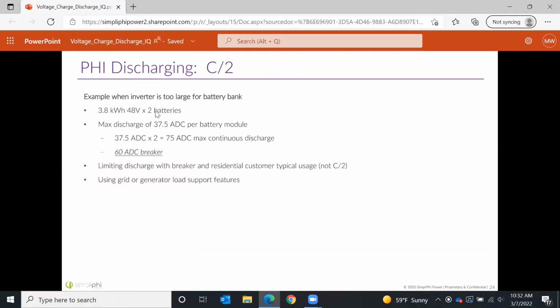We've got two batteries and they're 48 volts, so their max continuous discharge is 37.5 amps each. This is 75 amps total. And to protect the batteries, we're going to use a 60 amp breaker. We'll explain this a little more in detail as we go on. But first and foremost, when I see a 60 amp breaker and each of those batteries have an 80 amp surge for 10 minutes, there's almost no way that you would be able to utilize your surge capacity if you have a breaker on the branch specifically to limit the continuous discharging of the battery. So I think that overcurrent protection should be used for protecting wires, not batteries. However, let's just move forward with the example.